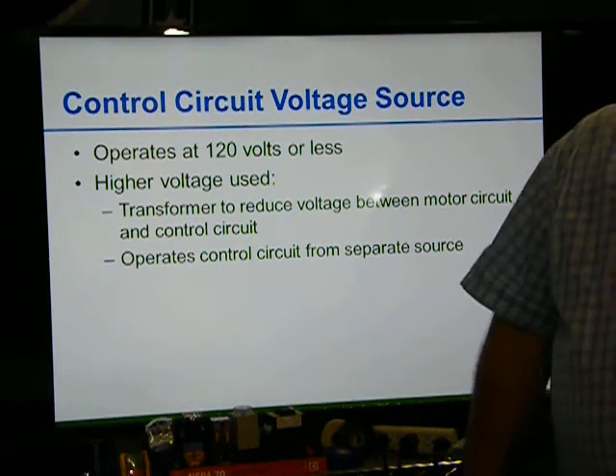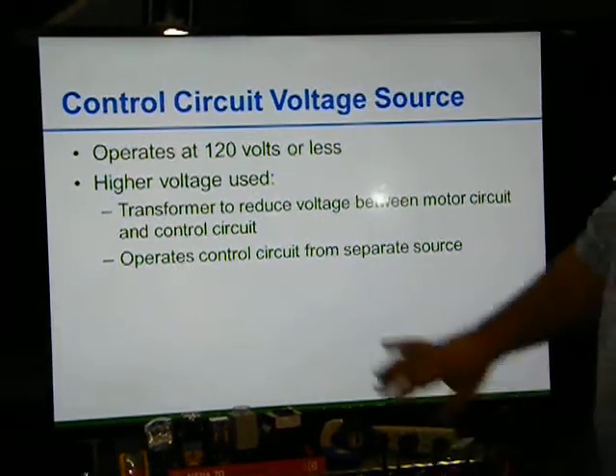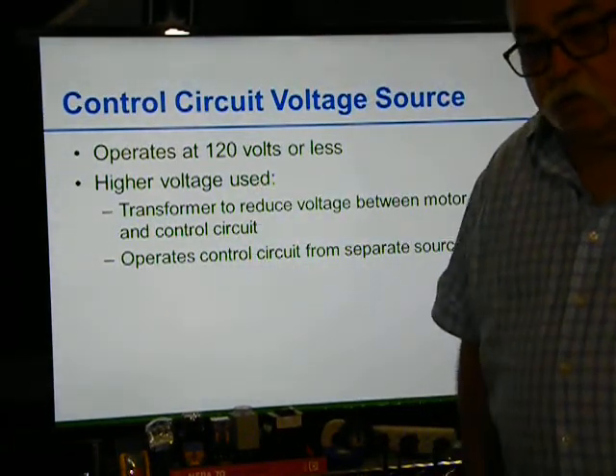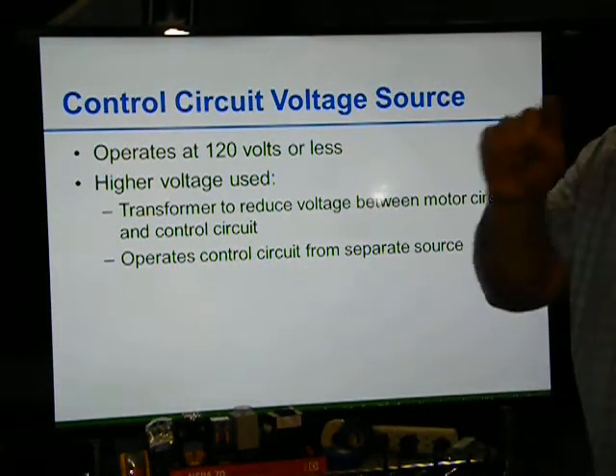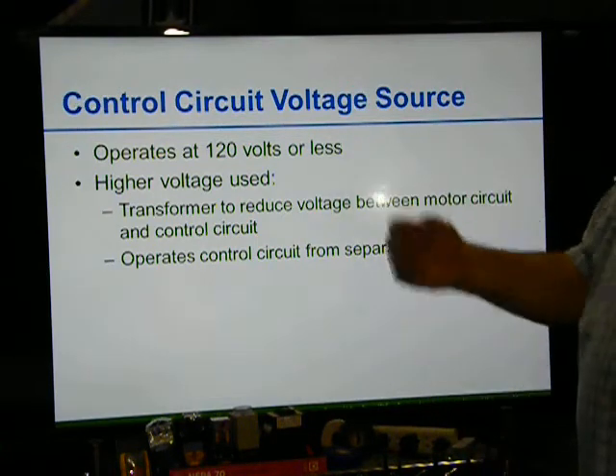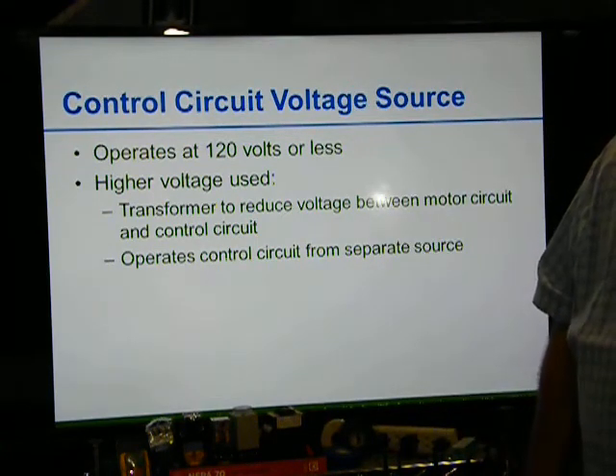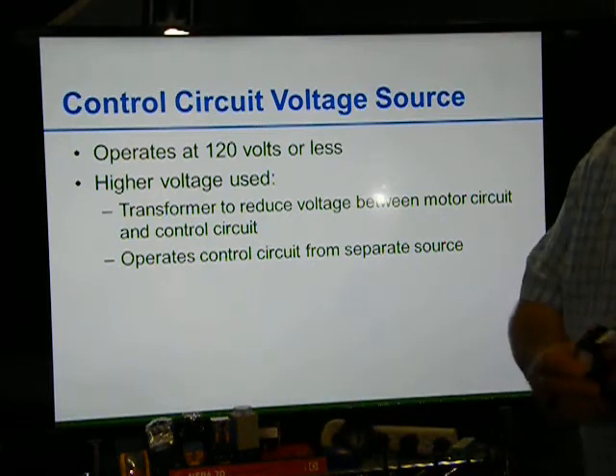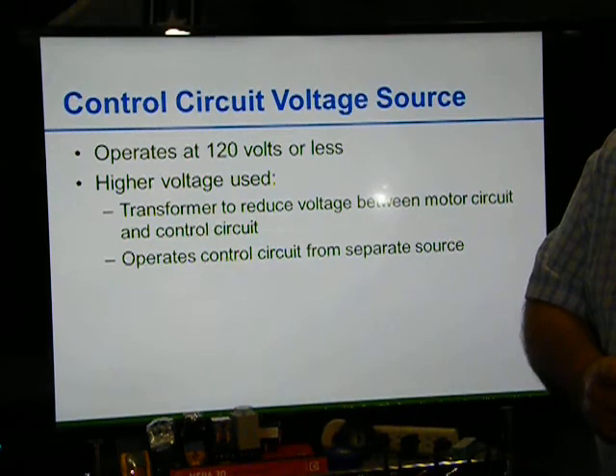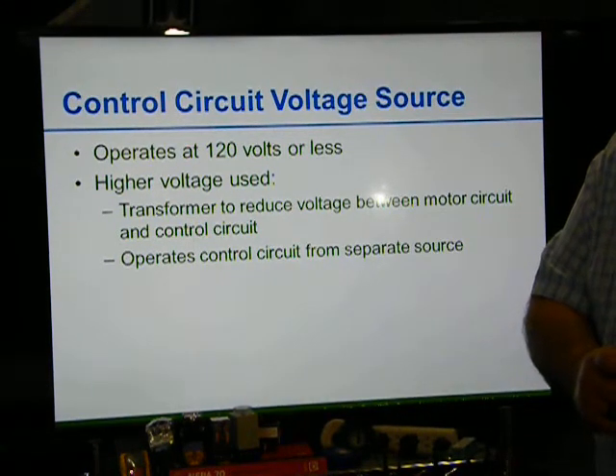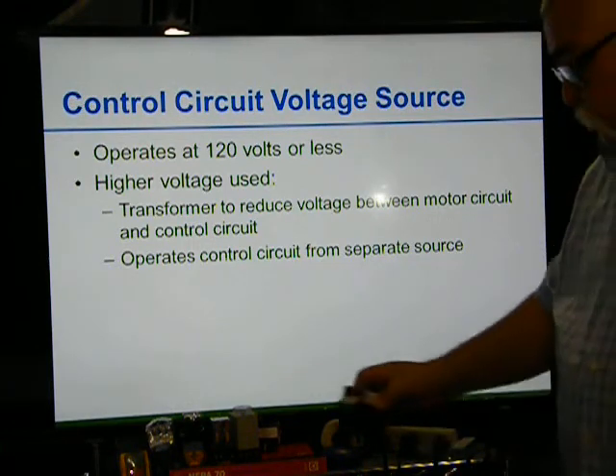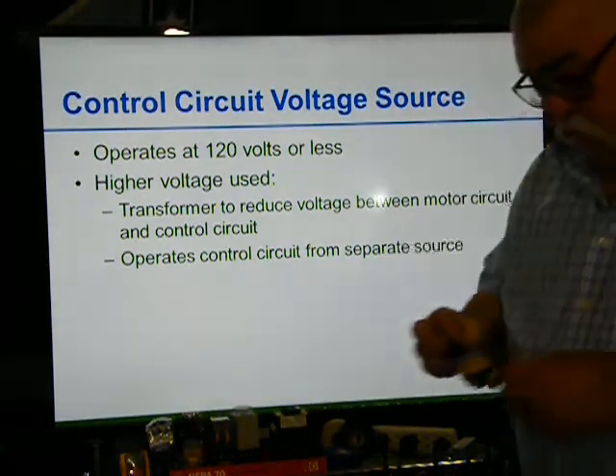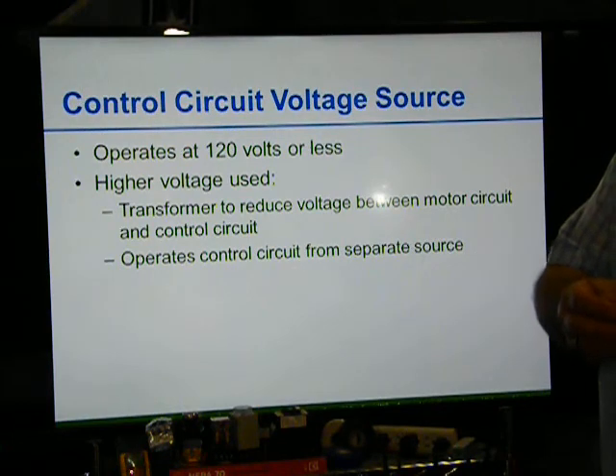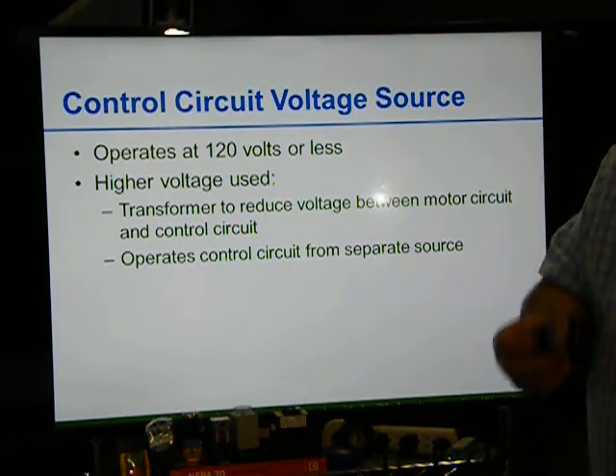Or you set up a transformer within your motor starter, and then reduce the voltage so your stop-start switches are at 120 volts or less. Your contact, your coil, is at 120 volts or less. So it's all according to whatever voltage you want for the equipment you're using. These switches are good up to 220 volts.